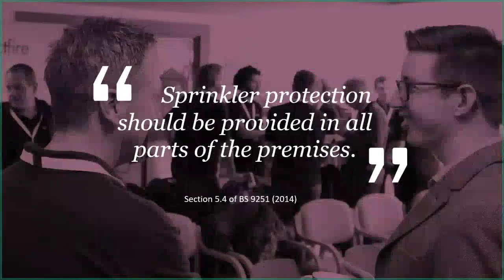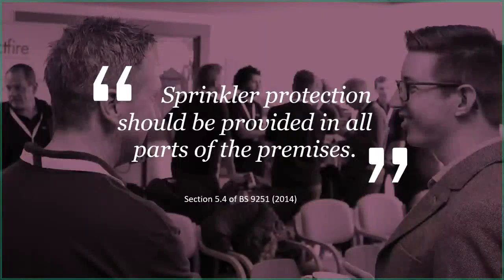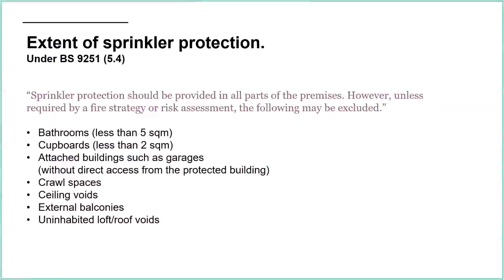There's a similar quote taken from BS 9251, the domestic and residential standard, where it says sprinkler protection should be provided in all parts of the premises. I'm sure there is a very similar statement in 16925 as well, which is the European standard for residential and domestic sprinklers. However, section 5.4 in 9251 talks about some exceptions - sprinkler protection should be provided in all parts of the premises, unless required by a fire strategy or risk assessment. The following areas may be excluded.